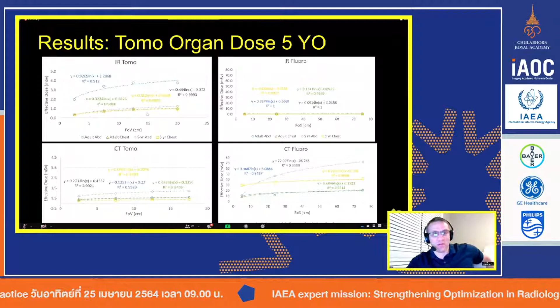And when you compare that to the actual CT itself, so doing just a normal helical CT of the chest or the abdomen, you can see that they were mostly the same, but a little bit lower than the cone beam CT from the C-arm. So cone beam CT, for all intents and purposes, used to be higher dose, much higher dose, several years ago than taking the patient down to a normal CT and doing your biopsies there. That's mostly changed, at least on the system that I have that we tested. And I think it's true for most systems as we've looked at this.